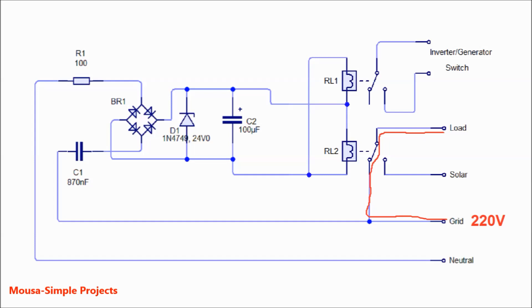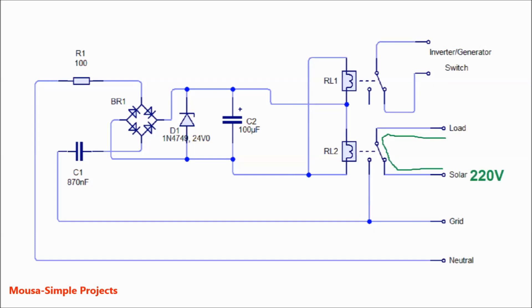Before a power outage, when electricity is coming from the electric grid, the relay runs and connects the electric appliances to the grid. During a power outage, the relay deactivates and connects the appliances to the solar inverter or gasoline generator. The second relay is used for switching the solar inverter or gasoline generator on and off, instead of leaving them running all day long.